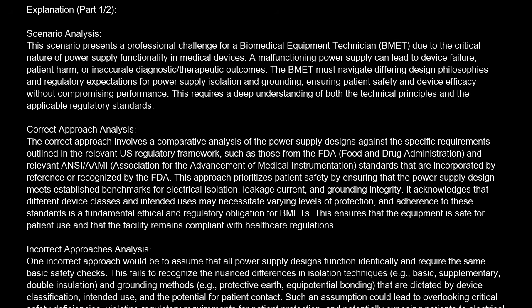Incorrect approaches analysis. One incorrect approach would be to assume that all power supply designs function identically and require the same basic safety checks. This fails to recognize the nuanced differences in isolation techniques, e.g., basic, supplementary, double insulation, and grounding methods, e.g., protective earth, equipotential bonding, that are dictated by device classification, intended use, and the potential for patient contact. Such an assumption could lead to overlooking critical safety deficiencies, violating regulatory requirements for patient protection, and potentially exposing patients to electrical hazards.